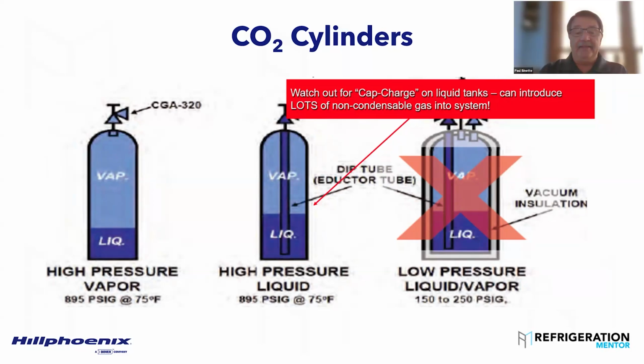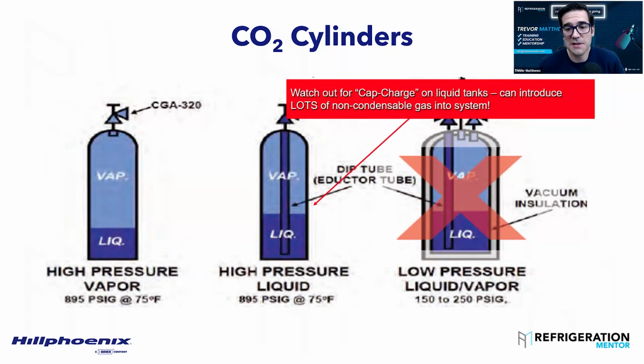And don't set your bottles outside in the winter. You want to have a minimum of, I think we just put something out for Canada, a minimum of 700 PSI on that thing. That's like 52 degrees. Outside at 70 degrees is not going to work here in Canada. 52 degrees is lower than it is here right now, and the sun is shining.